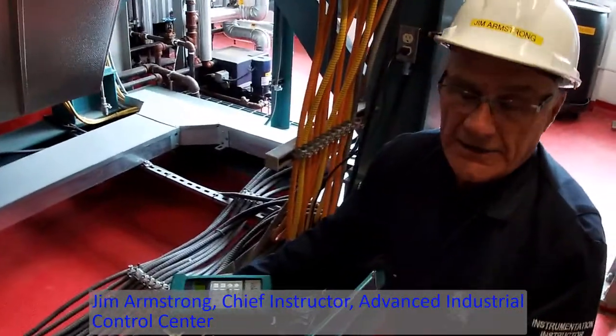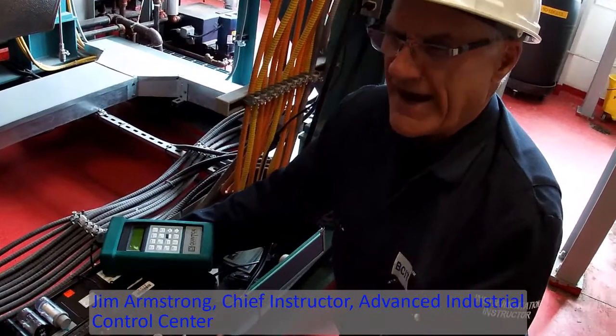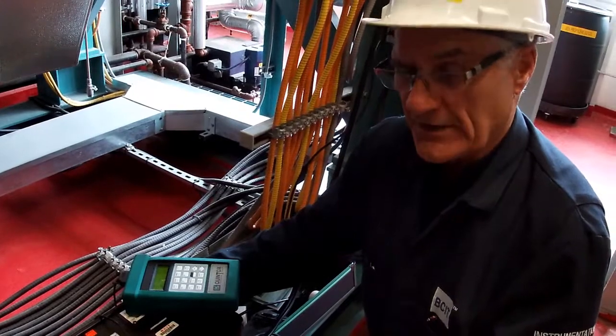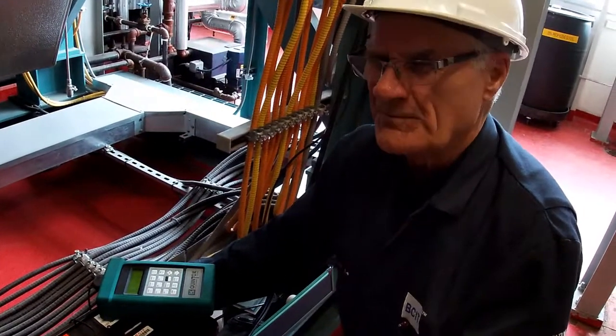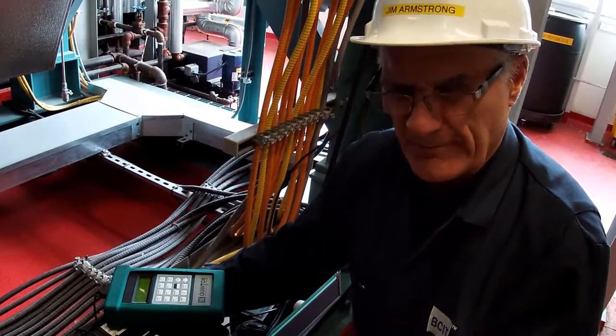This is a Kane May Quintox oxygen and combustibles analyzer that monitors NOx — that is NO and NO2, and the combination of those two is NOx — and it measures SO2. It measures the actual duct pressure, oxygen, and carbon monoxide.